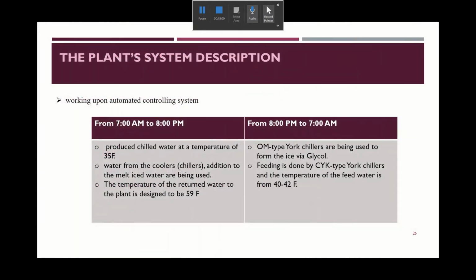When it comes to the plant system description, the plant works through an automated controlling system in the central controlling room inside the plant, where the operational state of the plant equipment and university buildings is monitored through monitors. From 7 a.m. to 8 p.m., the plant produces cold water at a temperature of 35 Fahrenheit through pumps to feed the assigned buildings. Throughout this period, the cold water from the chillers, in addition to the melted ice water, is used. The temperature of the water returned to the plant is designed to be 59 Fahrenheit. Mechanical cooling devices are used at a minimum to conserve energy while increasing operational efficiency. While from 8 p.m. to 7 a.m., feeding is done by CYK York chillers, and the temperature of the feed water is from 40 to 42 Fahrenheit. Meanwhile, OM York chillers are being used to form the ice via glycol.